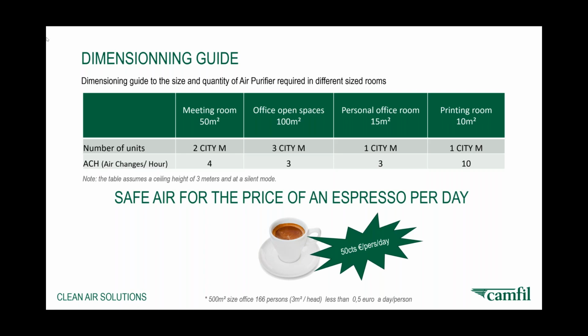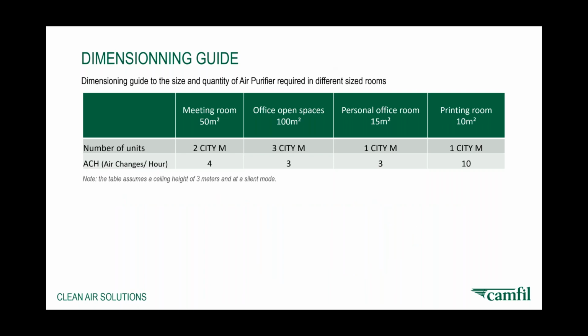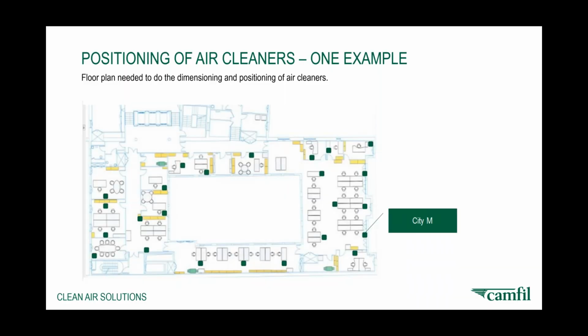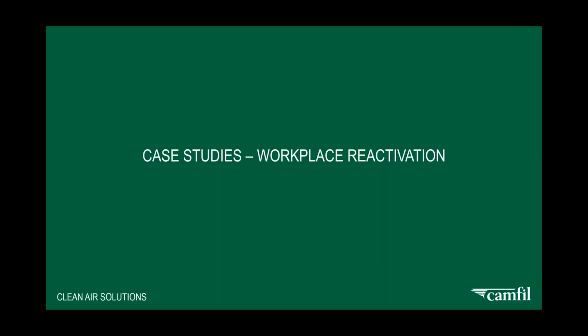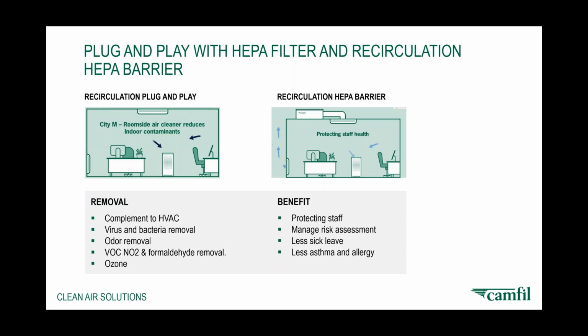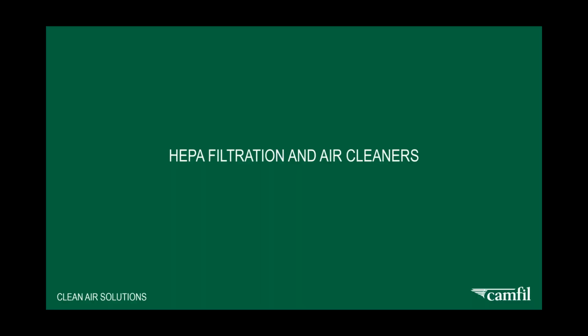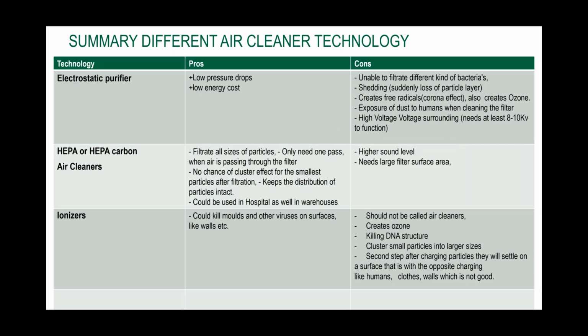Yeah, they are. If you look at the pros and cons, we had it earlier on. Yes, electrostatic air cleaners work. Yes, they work typically, in my opinion, for large particle sizes. An electrostatic air cleaner creates positive or negative charges onto which the particles sit. Once the power is there, that charge is maintained and the dust is stuck to the electrostatic plates. If the power changes or the current drops, you can have a release or a shedding of a particle, and that's the problem. They don't trap dust inside a media or inside any substrate. It's collecting on a plate, and you've got the possible issue with shedding.